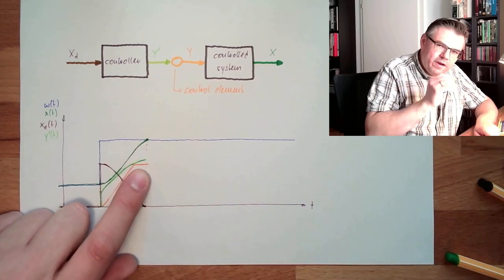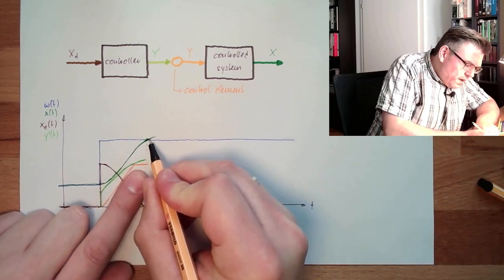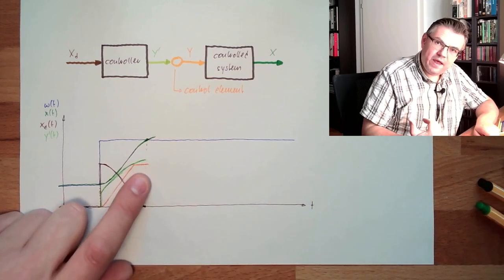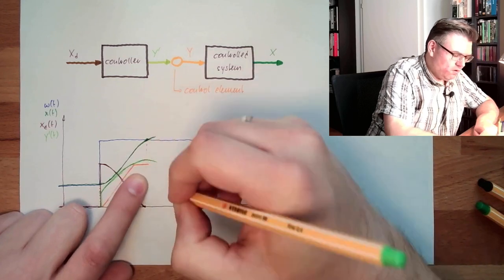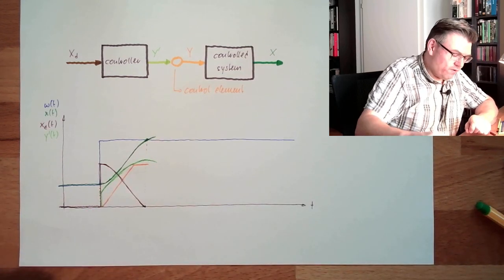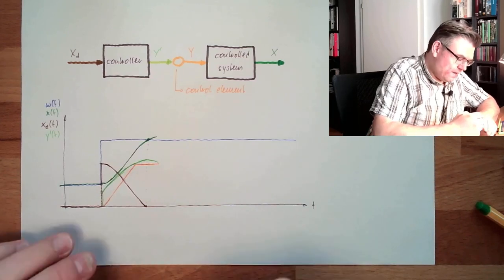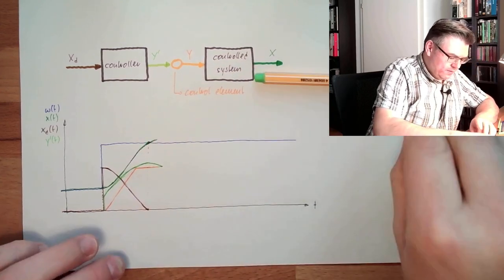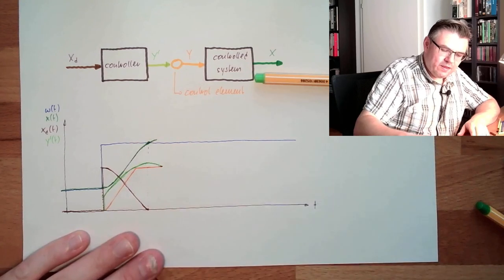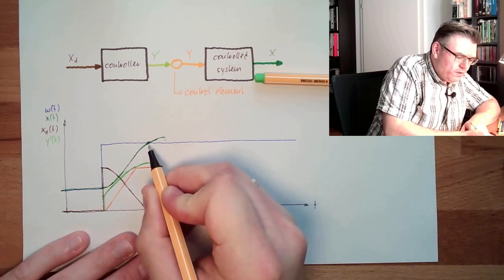And we would, of course, expect our controller immediately to react and go down with our correcting variable. It does, but only internally - this is going down now. Externally, I do not recognize it because I am at the maximum. I will have to wait until this internal value gets smaller than the external maximum, and then they will move together. Up to that point in time, we will simply grow, and maybe grow even further.